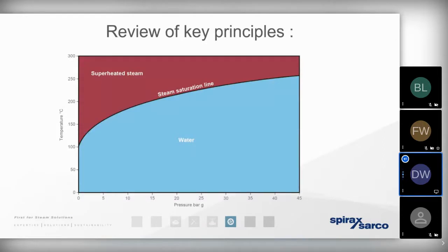We also know that we've got that pressure to temperature relationship that exists in both the steam and the condensate. So when we're distributing steam under pressure, let's say 10 bar gauge, we know that the temperature of the steam is 184 degrees. But if we want to utilize steam at a lower temperature at the process, let's say we've got a heat exchanger that only requires 132 degrees of energy on the primary side, well, we can achieve that temperature simply by reducing the pressure.